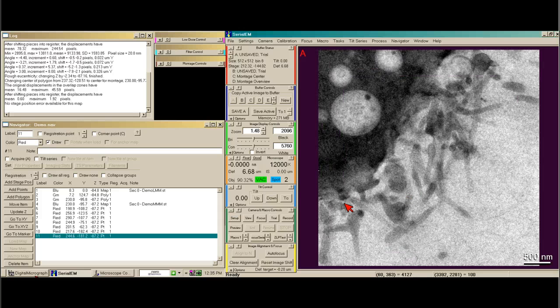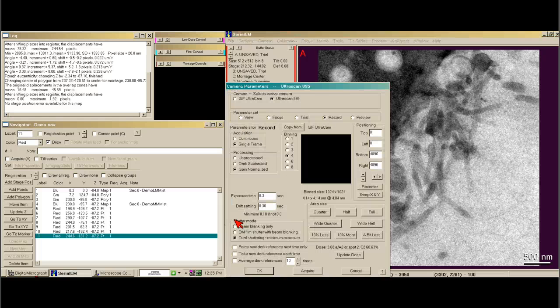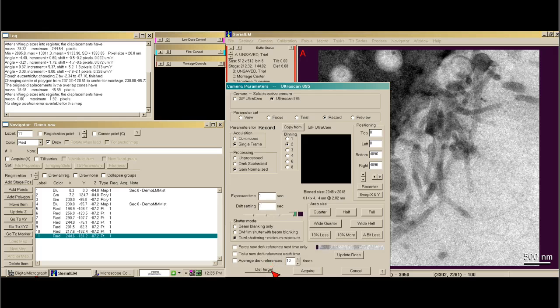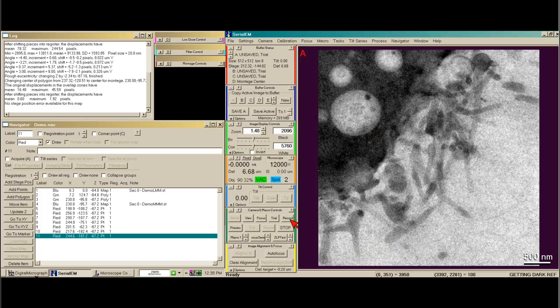Now what I want to do is set up my record. I say 'Set Up,' and my record was at bin by four for mapping, but now I want it to be bin by two. I want to increase the image exposure time as well as drift settling. Now I can take a record image and see what this looks like.